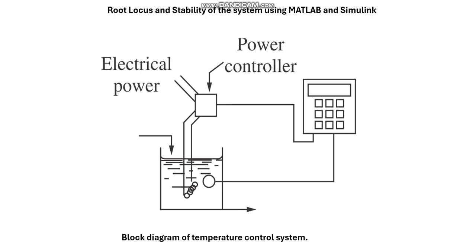This is a feedback process control system for temperature control inside a tank. We have a sensor here that senses the temperature and sends a signal to the controller. The controller compares the temperature to the set point, and if there is some error it takes action and sends the signal to the final control element, which may be electrical power or steam flow rate.